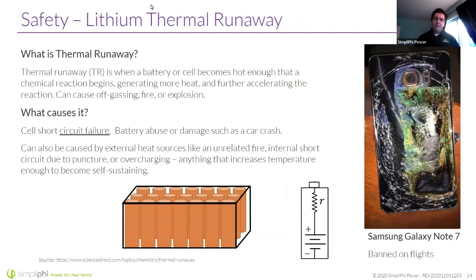So what is thermal runaway? Well, when a battery becomes hot enough, a chemical reaction can begin, and that can generate more heat, and that can accelerate the reaction. This is known as thermal runaway. So you heat it up enough that there's this chemical reaction, and that reaction generally results in off-gassing, which may be a flammable gas, which in turn itself has a thermal event. And now we've got runaway, potentially runaway with propagation.